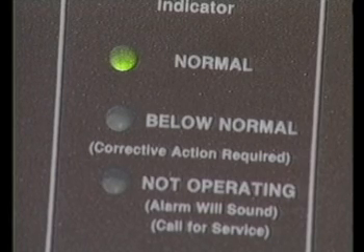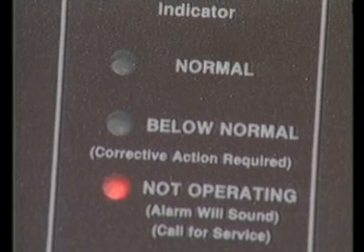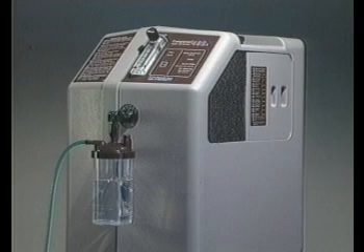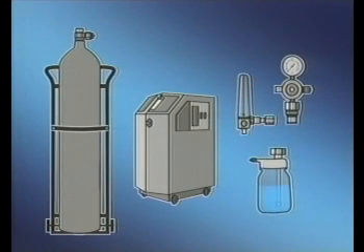If the concentration of oxygen falls too low, an orange, then red warning light comes on. If the concentration continues to fall, the machine switches itself off. The source of oxygen you use will be determined by what is available in your hospital. Having connected the items which allow the oxygen flow to be controlled, monitored and transported to the patient, you are then ready to select the equipment to deliver the oxygen to the child.